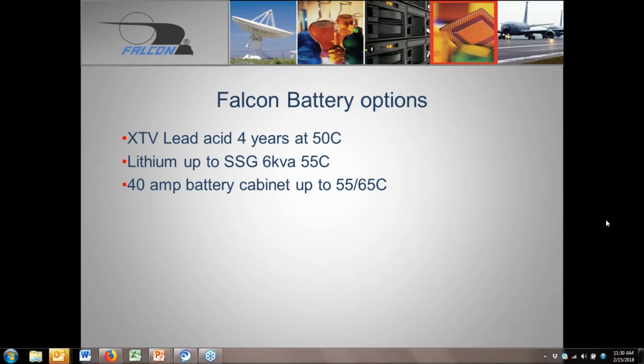That 40-amp battery cabinet is lead acid based, not lithium. It's 5U in height and gives the ability to run for hours instead of minutes. We've had 66 of those installed at an application in LA since 2011, in an outdoor enclosure under the freeways, and we're just now starting to replace some of those batteries 7 years later.